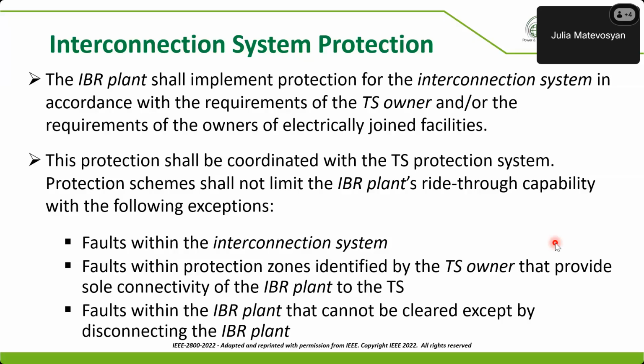So in the standard we did not go into a whole lot of detail about specifying the protection for the interconnection system or tie line. We simply said that the plant shall implement protection in accordance with the requirements of the transmission owner. Some owners might prefer differential protection. Some transmission owners might prefer simple step distance based protection. There could be other options out there. So the standard simply said, follow the instructions provided by the transmission owner. Protection shall be coordinated, right, with the transmission system protection.